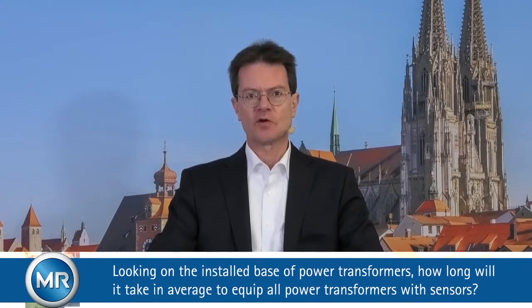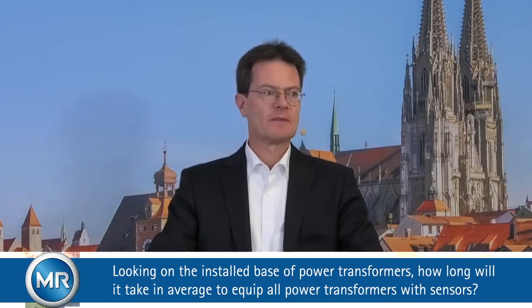There is a huge fleet installed with a different background of age, manufacturing, function in the grid, and their contribution to security of supply. So I do expect that intelligent sensoring is first applied where the criticality or the value of the transformer is highest to the grid operator, and then it will take its certain speed to cover the rest of the fleet. Most importantly, our solutions can be retrofitted, and it's not always the size of the transformer which determines the value or the criticality for the operator.